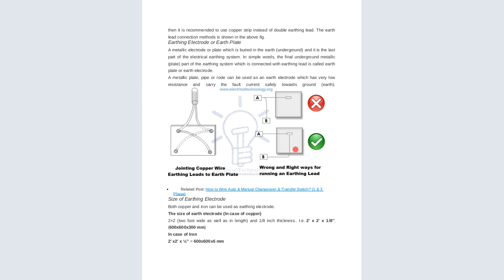Now this is the right joining when they are joining like this, and these are the wrong and right ways of joining. So this one is a wrong joining. They need to meet at the plate, not one meeting at this point and another at this, so that they can equally reach the ground. So you can see this is the wrong connection. The first one, the one I'm pointing at, is the wrong connection, and the second one is the right connection, meaning that all the lead cables, the lead electrodes coming from the appliance, must reach the earth plate.